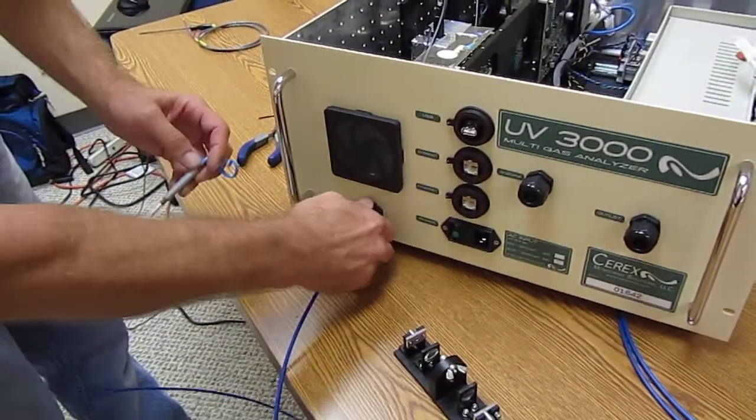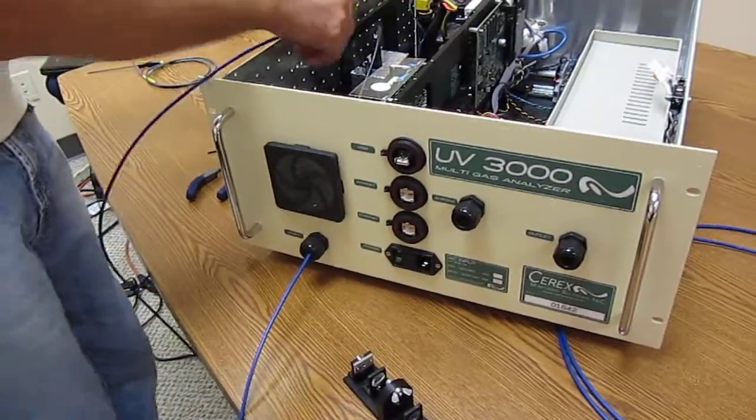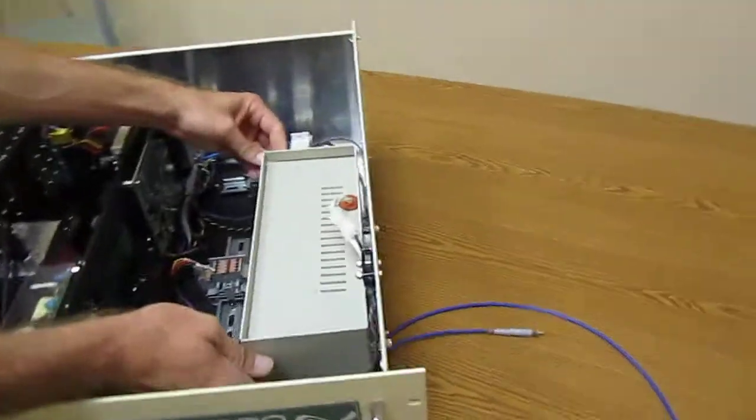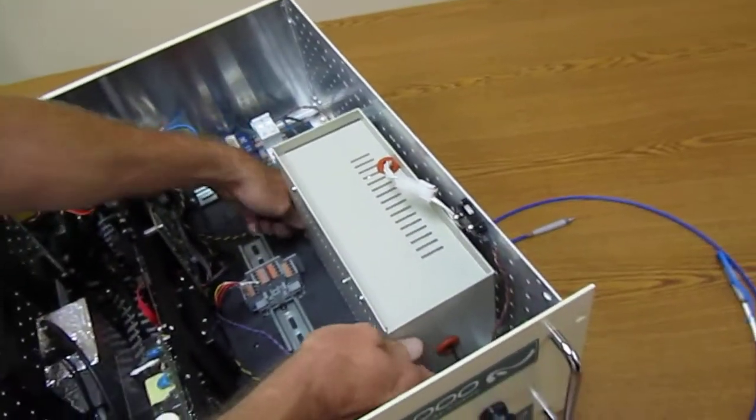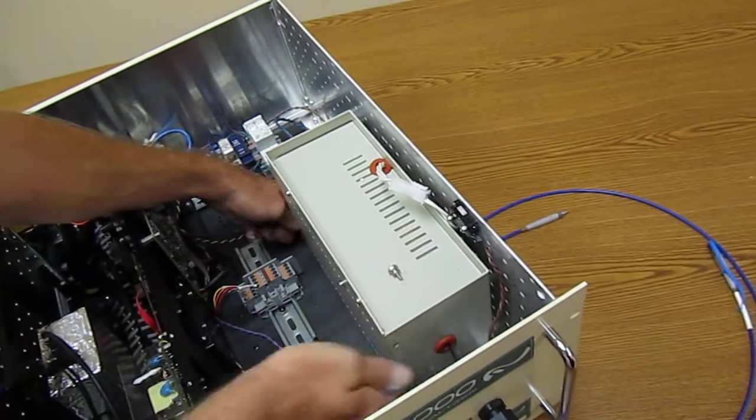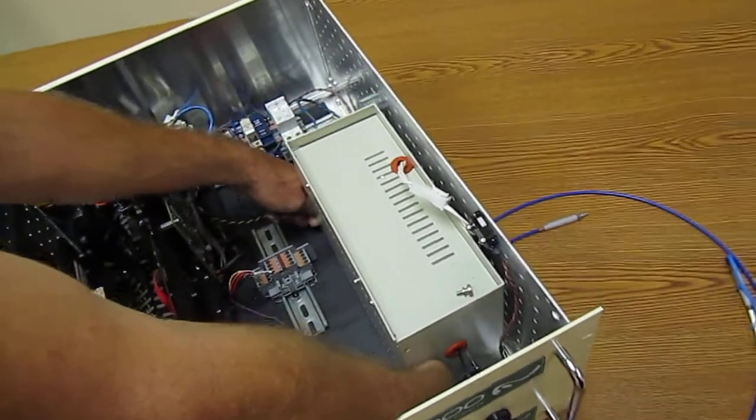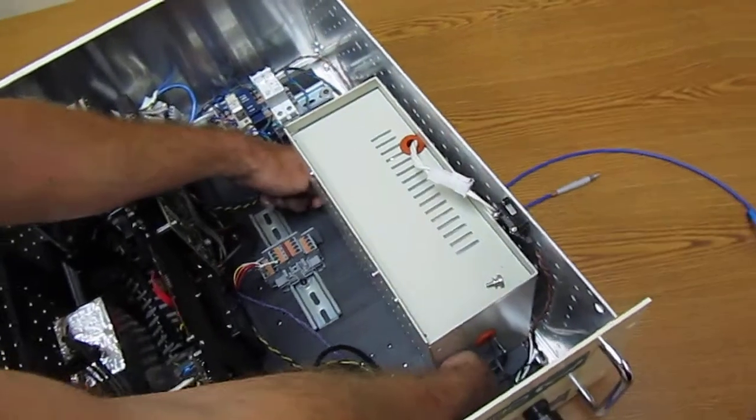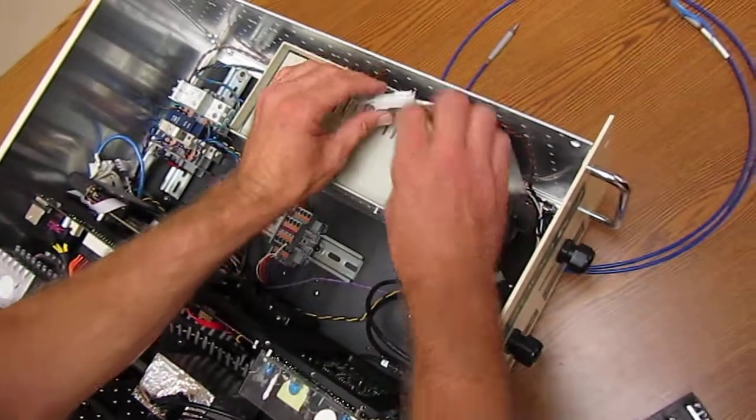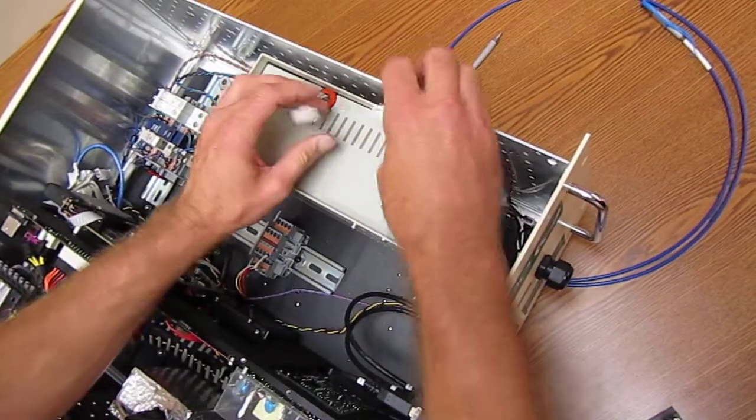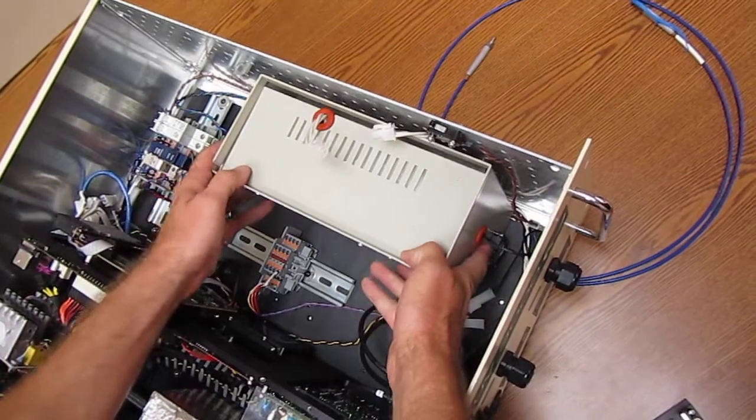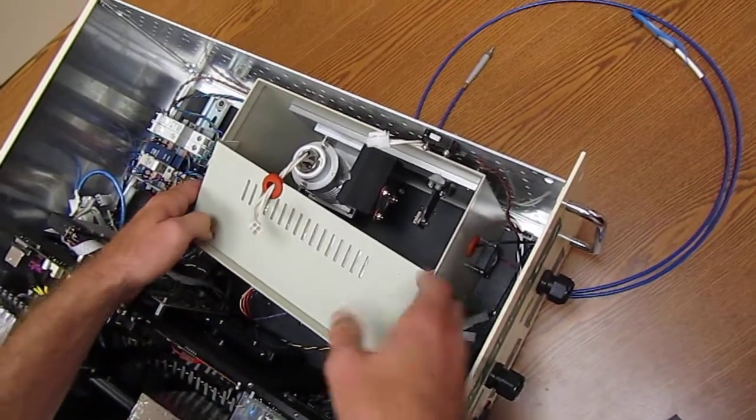To install the outlet cable, fiber optic cable, unscrew the thumb screws on the source lamp enclosure, disconnect the molex connector, and slide the housing away.